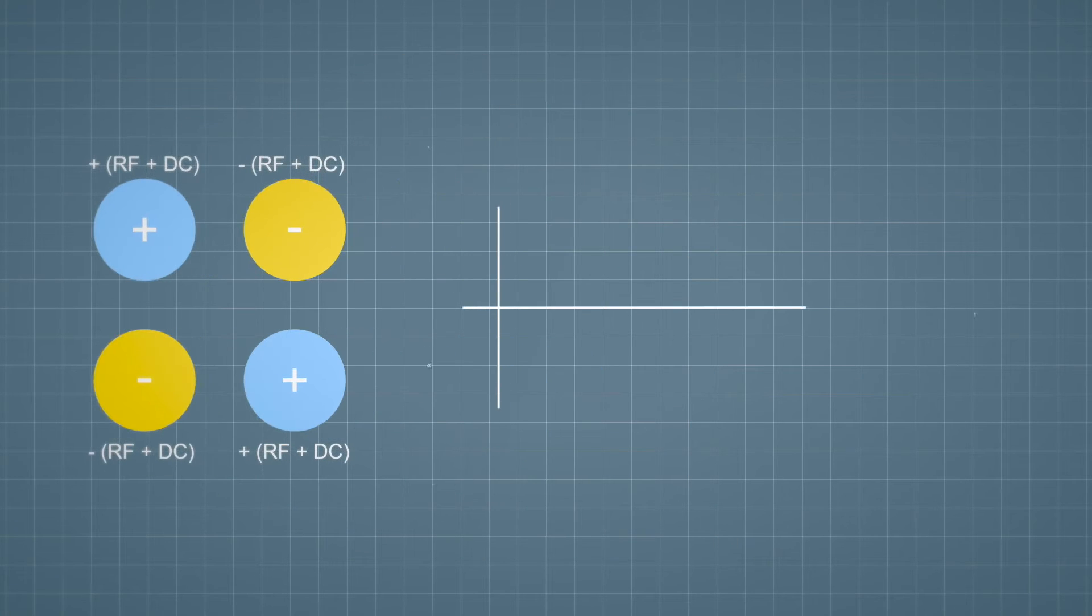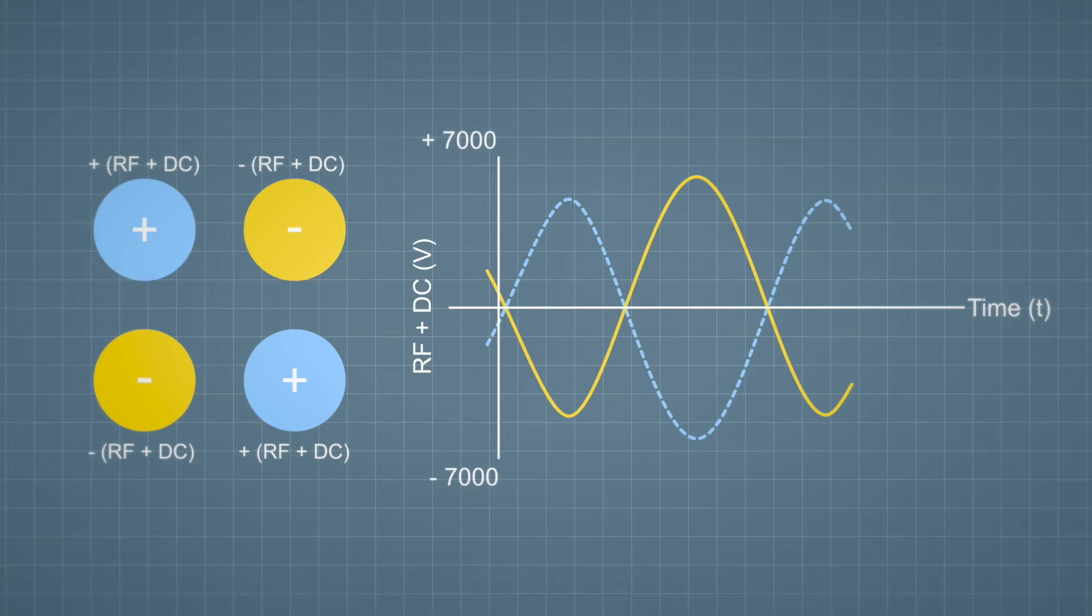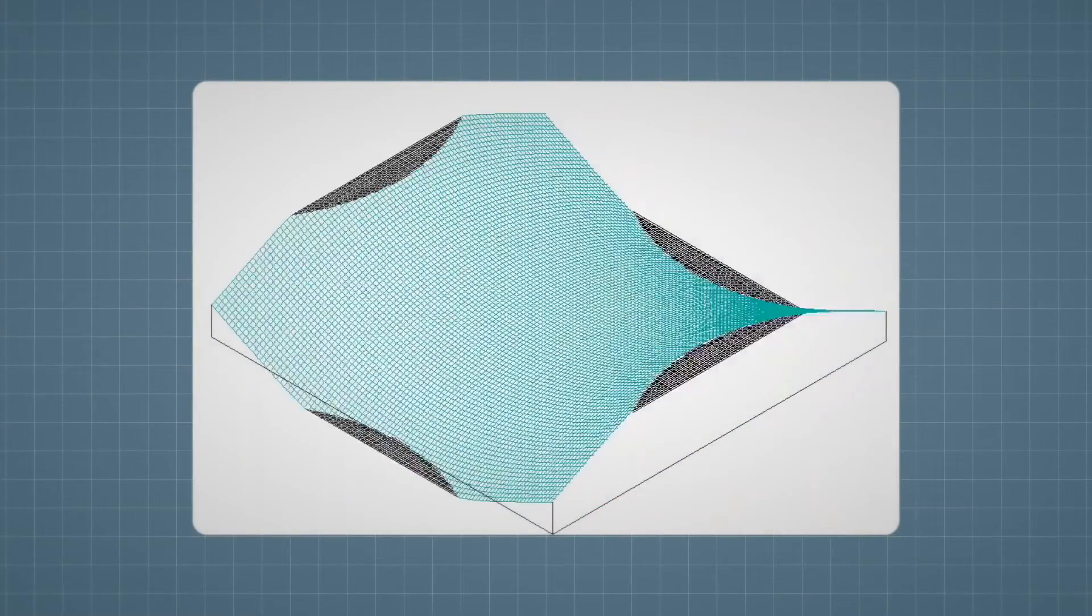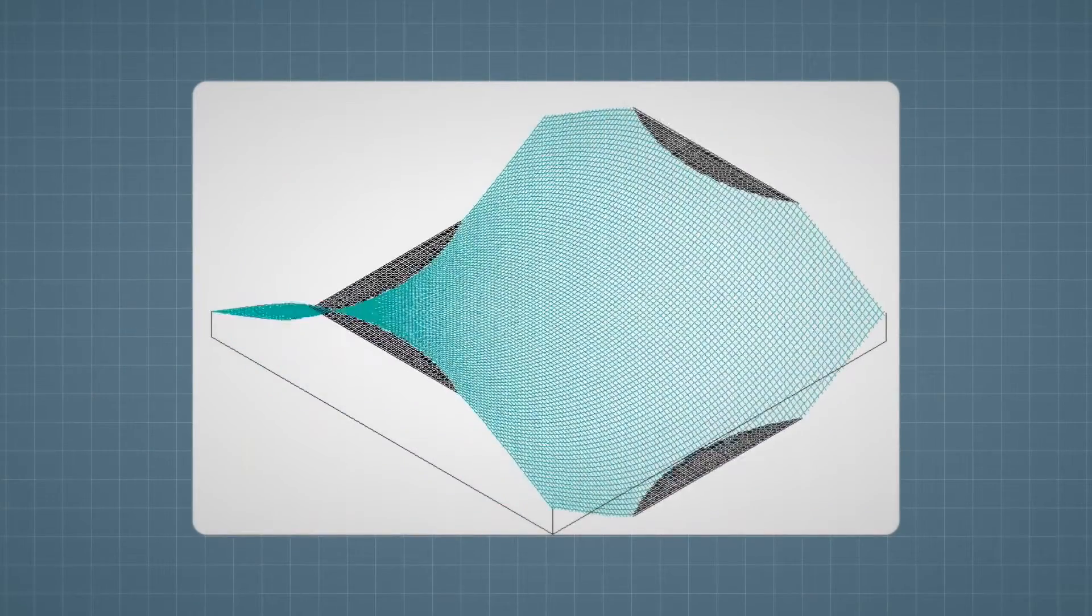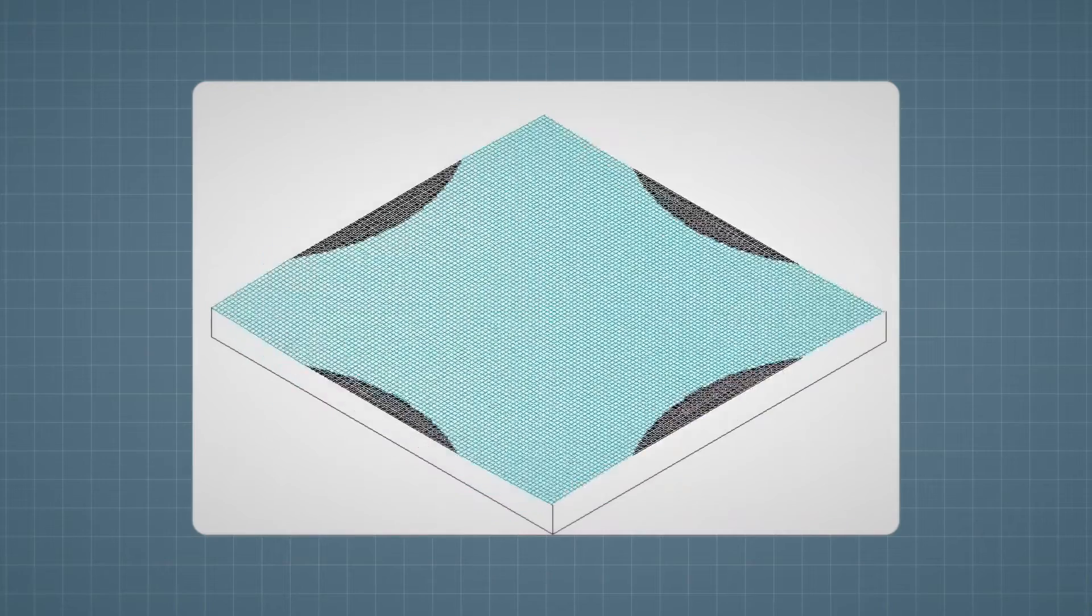Static potentials, or DC voltages, and alternating potentials, or RF voltages, are applied to the quadrupole rods, with one pair of rods having the opposite polarity to the other pair. These voltages create a fluctuating electric field between the rods. The field oscillates, as shown, typically at frequencies of approximately 1 MHz.